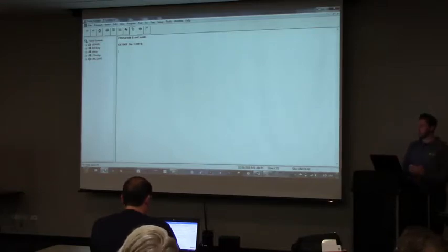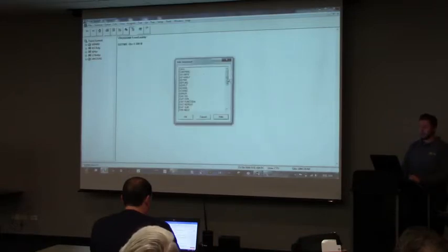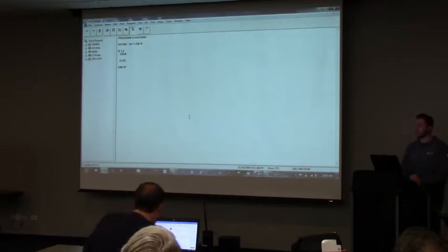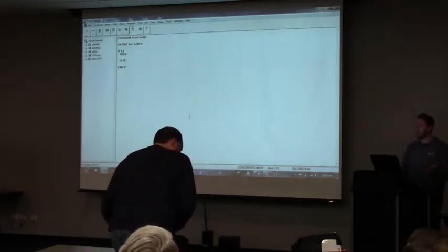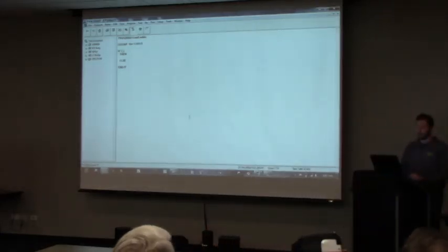Now I could get my statement here. So when I come up to Edit again, and I hit add statement, I'm gonna scroll down. This is pretty much the bread and butter of CPL, the if then else statements. So I'm just gonna hit if else, and it inputs it right there for you already. So I'm gonna write my statement up here. If outside air temperature is less than 55, then enable economizer, else disable it. So just something real simple.